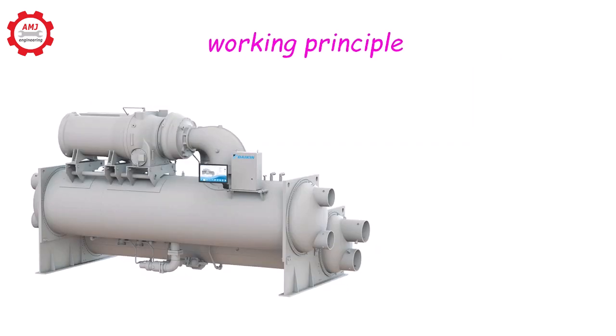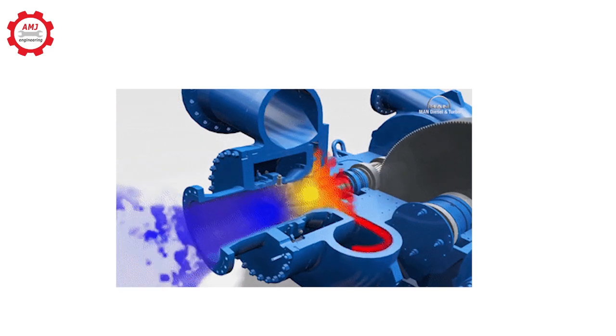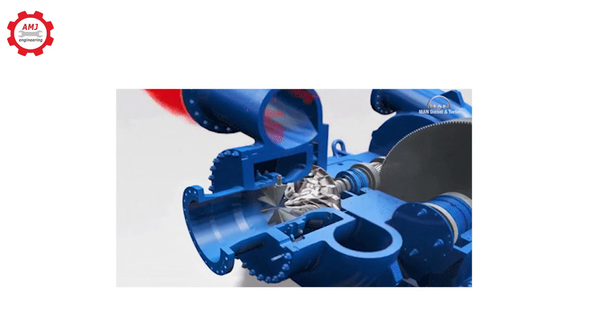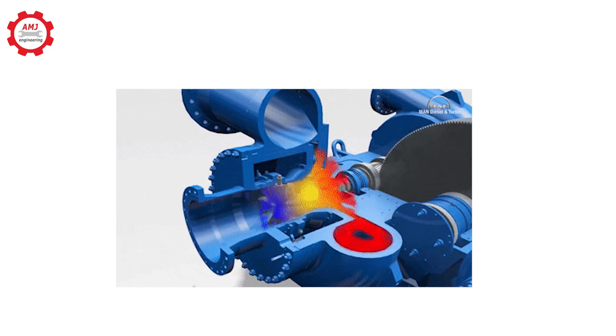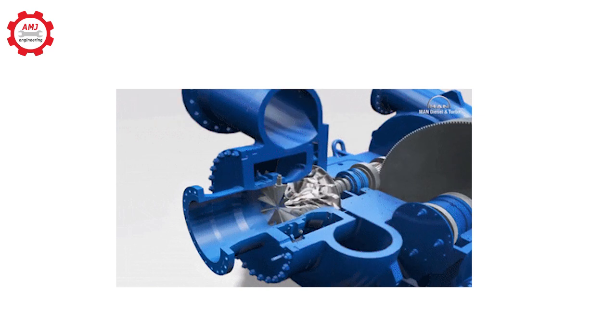What about the working principle of centrifugal compressors? Like centrifugal pumps, an impeller provides the force to compress the refrigerant vapor. The low-pressure refrigerant vapor enters the eye of the impeller. The rotating impeller adds kinetic energy to the flow which is then converted to an increase in pressure by slowing the flow through a diffuser.